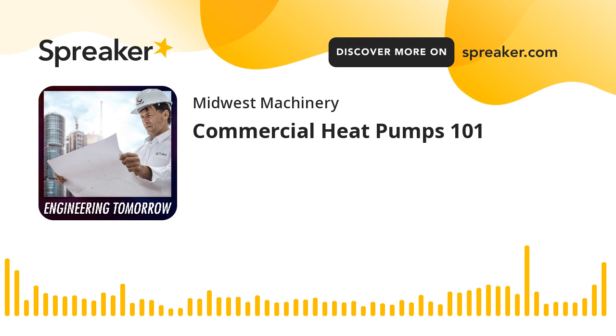Other than that, you're looking at hose kits for your water source heat pumps. Those are flexible stainless steel hoses that connect the heat pump to the actual piping in your loop. They allow for easy install and removal of the heat pump if you need to service it. And they also have isolation valves, usually a PT port so you can test pressure and temperatures if you need to. They have some sort of auto flow or circuit balancing valve so you get the right amount of flow through each heat pump. And sometimes they will have a two-way motorized control valve so that if the heat pump's not on, you don't have water going through it, and that'll help you save money on pumping costs. Other than that, that's pretty much the whole kit and caboodle there.